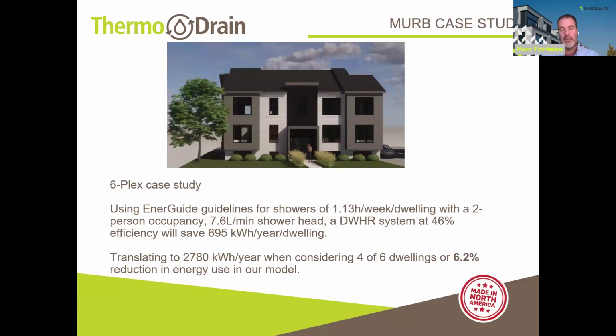So we have a 6 dwelling unit building, so 3 on each side. This 6-plex study that was done shows basically that, using EnerGuide guidelines with the drain water heat recovery system at 46% efficiency, we're reducing a little over 6% of the building's energy load. This building, I'll get to it in the next slide, has 2 drain water heat recovery units in it. And so for 2 units, you get that 6%. Usually builders have been finding that it's a good bang for your buck in terms of what investment needs to be put into the building versus the energy savings.